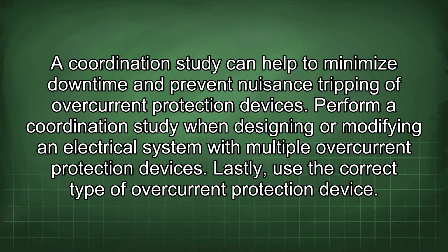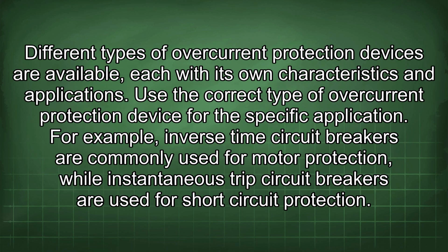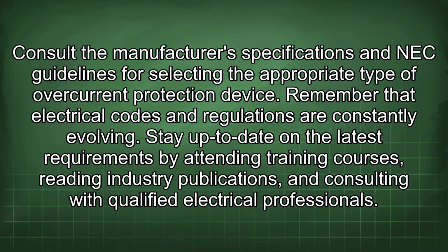Lastly, use the correct type of overcurrent protection device. Different types of overcurrent protection devices are available, each with its own characteristics and applications. Use the correct type of overcurrent protection device for the specific application. For example, inverse time circuit breakers are commonly used for motor protection, while instantaneous trip circuit breakers are used for short circuit protection. Consult the manufacturer's specifications and NEC guidelines for selecting the appropriate type of overcurrent protection device.